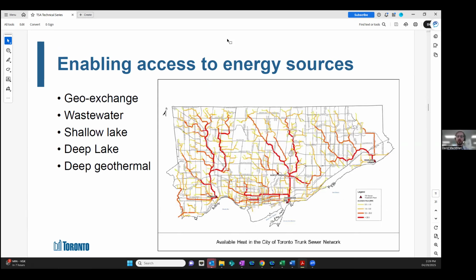One of the ways we enable access to thermal energy sources is by providing information. The map shows the city of Toronto and the trunk sewer network, the large trunk sewers with models and, in some cases, measured heat available in those trunks. You can recover heat from sewers and use it to displace natural gas. It's perfect temperature, requiring a little lift from a heat pump, but since sewage is typically 18 to 20 degrees Celsius, that's a lot less lift than you'd need from an air source or even ground source heat pump. Wastewater, which is just readily flowing and otherwise unused, provides a lot of heat that can be captured and used to displace gas in buildings.